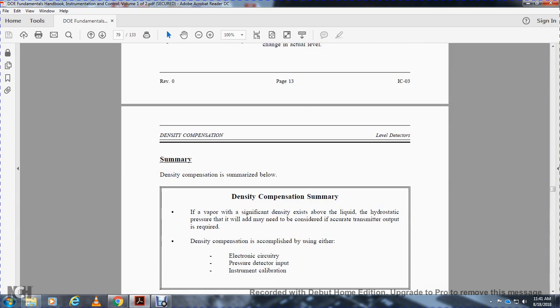Alright, summary. Density compensation is summarized below. The vapor has significant density that exists above the liquid, and the hydrostatic pressure for the wet leg will add immediately. To obtain an accurate transmitter output, density compensation is required, accomplished using either an electronic circuit with the pressure detector or input with the instrument calibration.